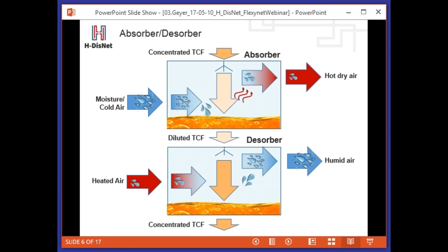So drying, industrial drying, that's the easiest process to be provided by absorption. We just need to take the humid air in the absorber to remove the humidity and to provide the hot, dried air again to the drying process. And the advantage is that it can run in air recirculation, and we can avoid a lot of primary air energy consumption usually required for drying, because we can base the drying process on the absorption, which is then driven by excess heat at other locations, other times, that is transported by the network.